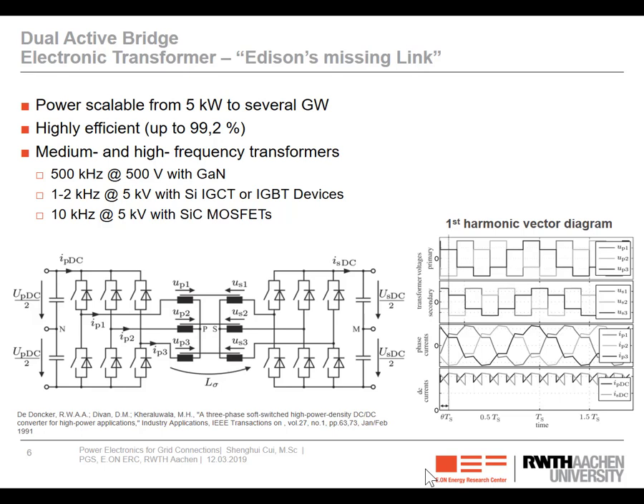So the benefit of increasing the frequency range of the transformer is that, for the same power rating, the higher the frequency, the smaller the size. And when we elevate the transformer operating frequency to 500 kilohertz, then we can have an ultra compact transformer design. And using today's silicon technology, for 5 kV medium voltage, we can operate at 1 to 2 kilohertz.